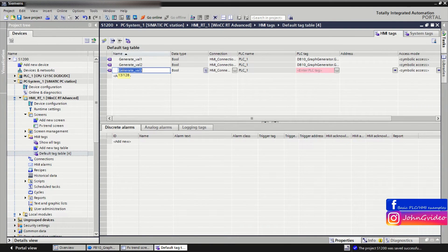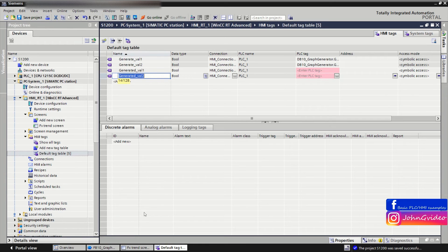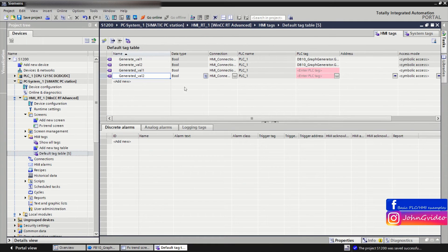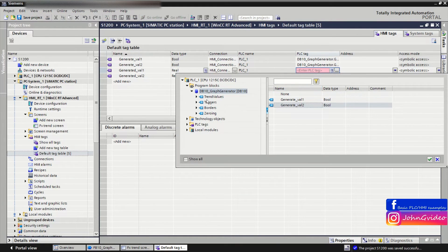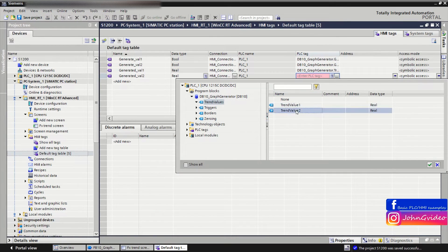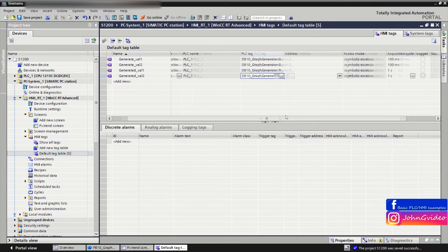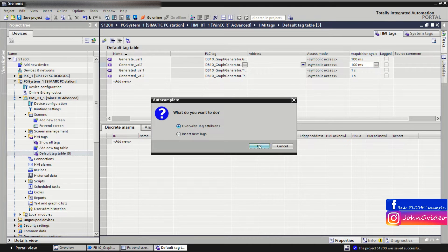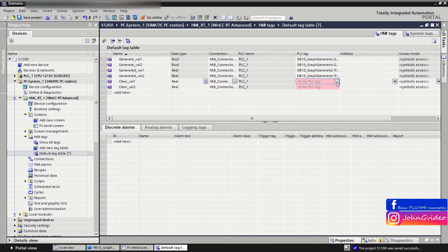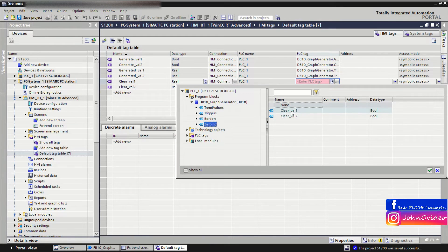Then we link 'Trend Value 1' and 'Trend Value 2' as the values of the trend, with data type Real. We set the connection and link the tags trend value 1 and trend value 2 with an acquisition cycle of 100 milliseconds. We also create 'Clear Value 1' and 'Clear Value 2' tags, linked to the corresponding tags in the data block.